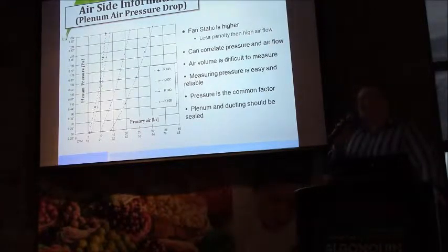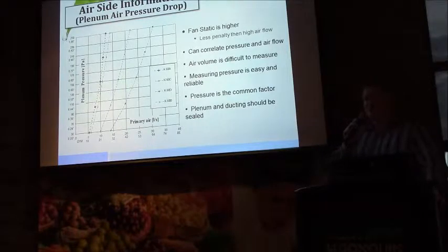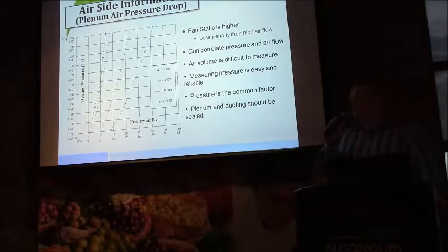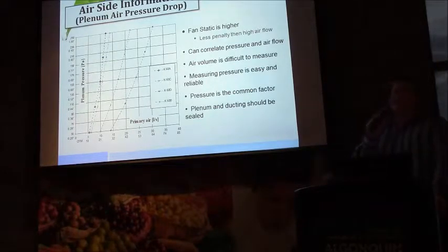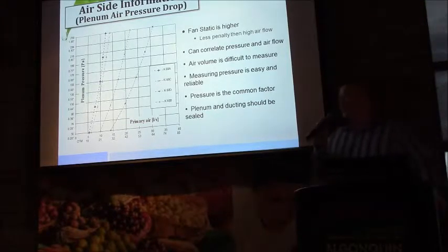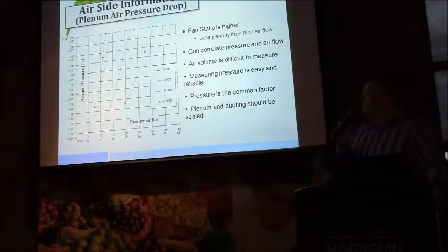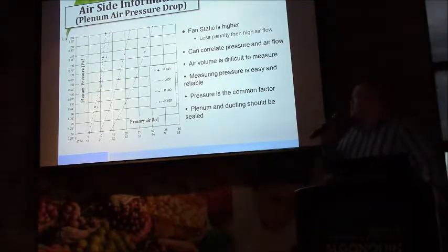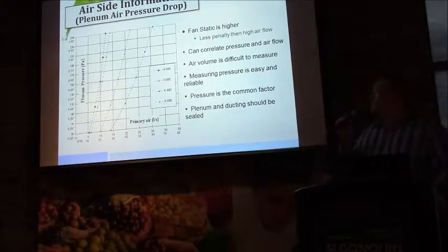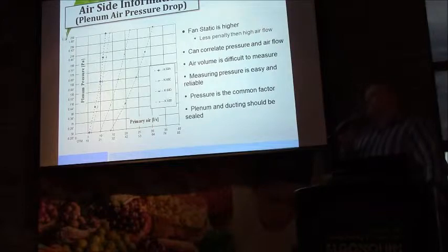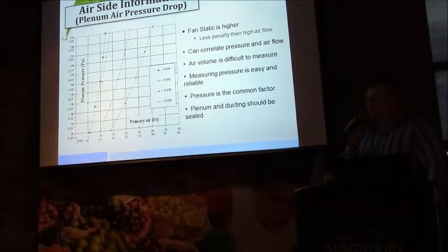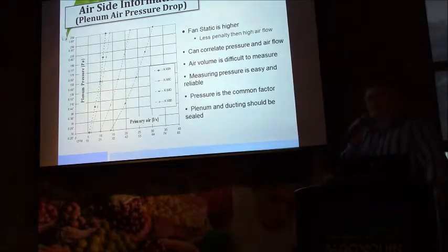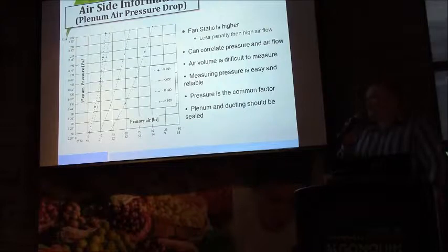The other benefit to that strategy is, frankly, the primary air handling unit must be designed to overcome the static pressure of the distribution ductwork, and as a consequence, the pressure is available to us. And so having that delivered to the beam, coupled to the fact that it delivers more total capacity and lowers the capital cost of the equipment, is a useful approach. In addition, because of the plenum static pressure that we have to generate at the primary air handling unit, if we were to design all of the beams in the spaces at lower plenum static pressure, we now have to introduce an obstruction in the ductwork to scrub off some of the pressure before it's delivered to the zone, and that has the potential to generate noise.